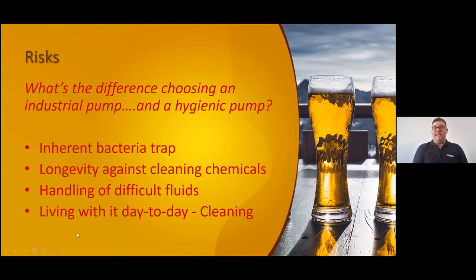Also living with it day to day, the cleaning, as mentioned, against the CIP. Can the industrial pump stand up to the rigours of the CIP that's needed for the hygienic applications? Also the environment that it's based in - is the motor to the correct IP rating for the wash down and things like that? So as important as it is for the pumped medium, it's also important to specify the correct materials for the environment that the pump's going to be based in.